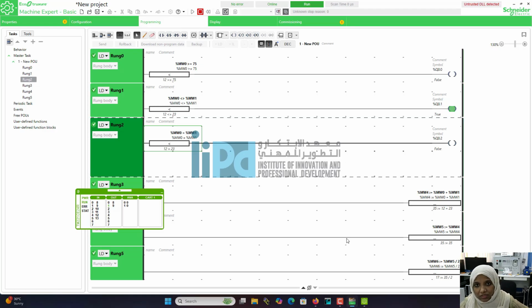In some cases, for some applications, you want fine values. For example, the value will be greater than 2.5, or I want to add a value called 2.5 to the sensor, or some kind of tolerance I have to give. In that case, I have to convert the format. Initially if it is an integer, I have to convert that into real, and then do the calculations with the real data type. Okay, so that's how the conversion happens.